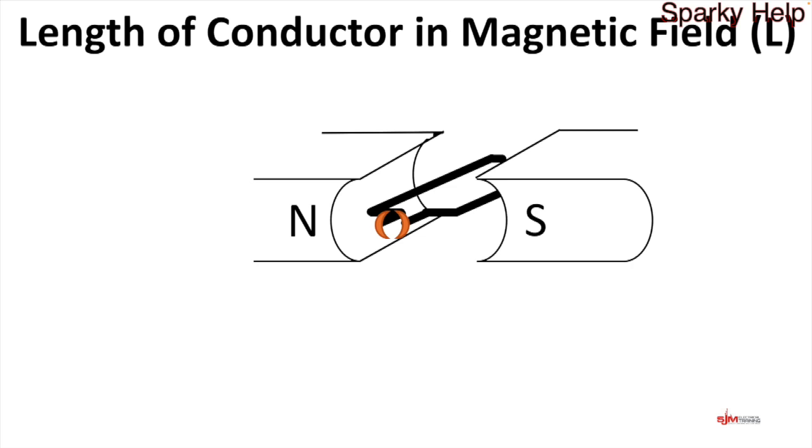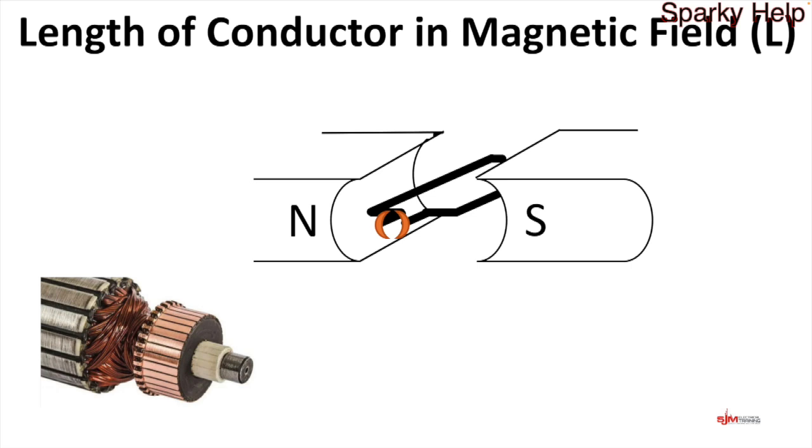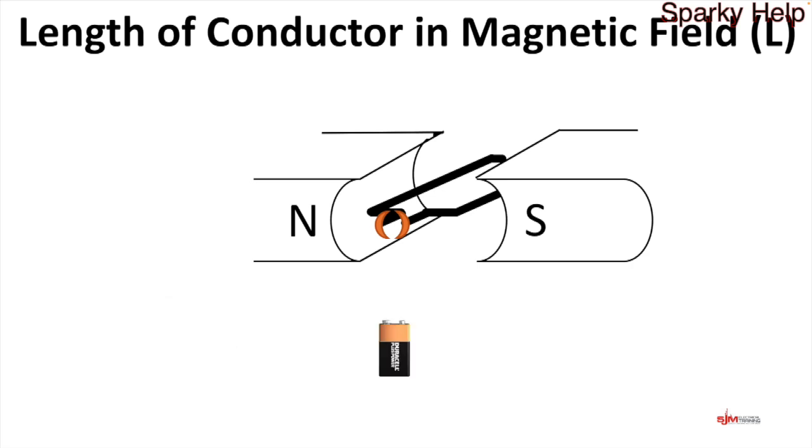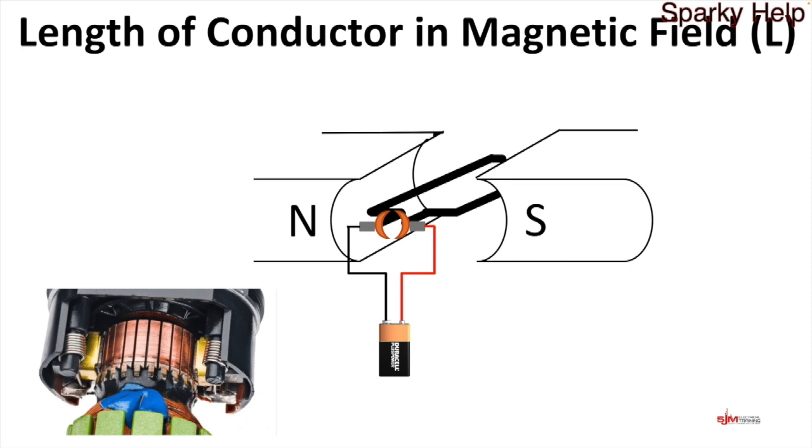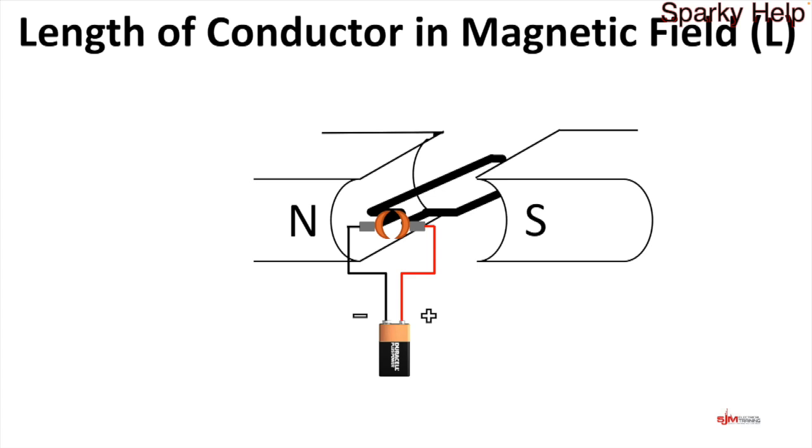How does this work on motors? You have one coil looped around that comes out to something called a commutator, which is basically two half segments of which we can now connect a battery to. They would connect onto this commutator which rotates because it's got bearings. You put carbon brushes onto them which make contact. In older drills you may have seen arcing in the little grills at the back. What you're seeing is the carbon brushes wearing down onto the commutator. If we apply current, current will flow through this conductor in and out.